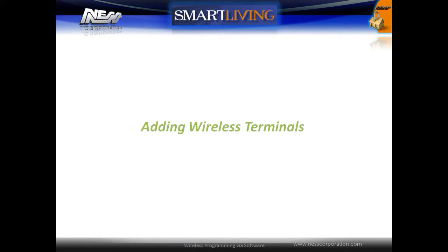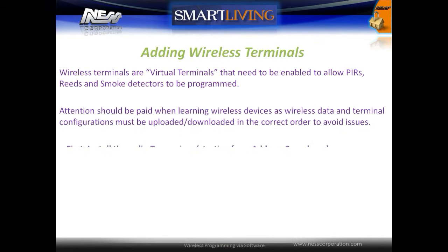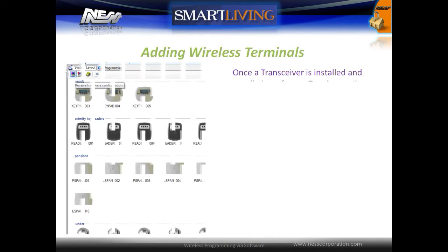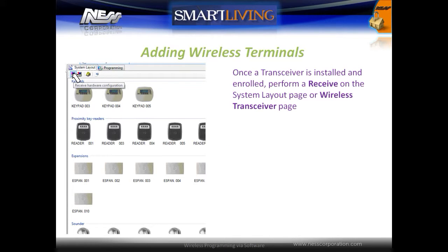Wireless terminals are virtual terminals that need to be enabled to allow PIRs, reed switches and smoke detectors to be programmed. Attention should be paid when learning wireless devices, as wireless data and terminal configurations must be uploaded and downloaded in the correct order to avoid issues. First, ensure the radio transceiver is installed starting from address 2 or above. Once a transceiver is installed and enrolled, perform a receive on the system layout page or wireless transceiver page to upload the transceiver.